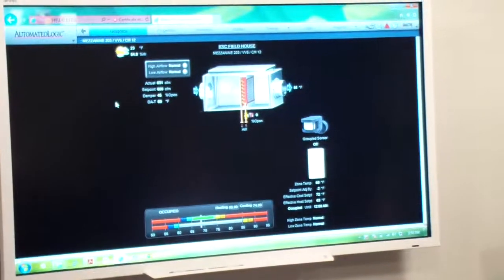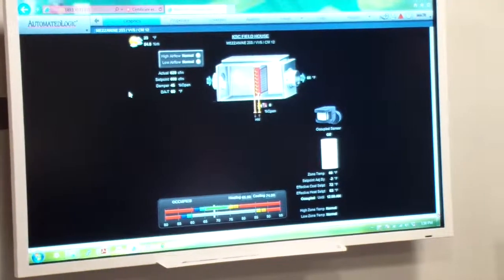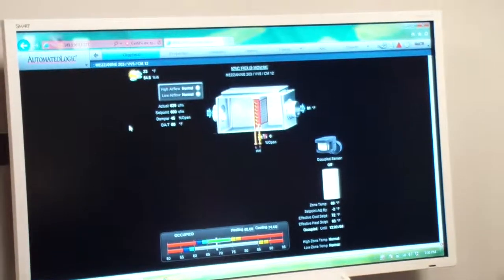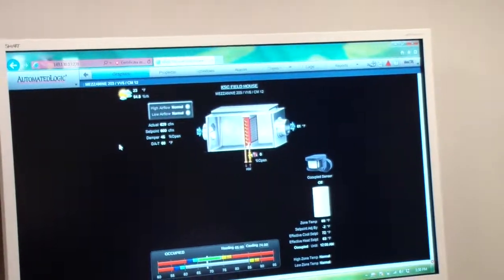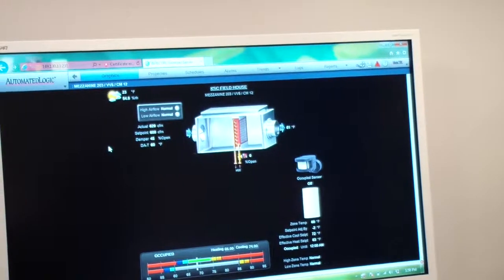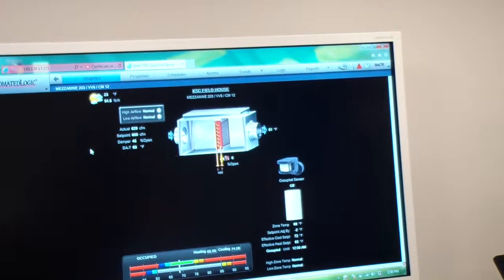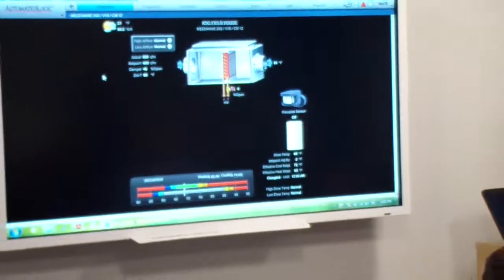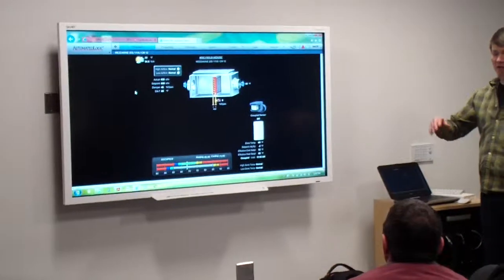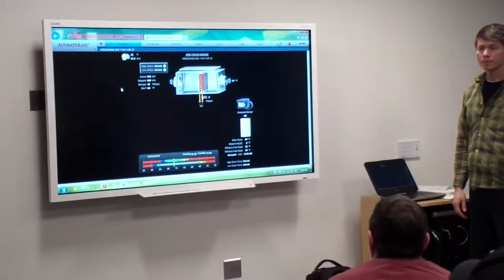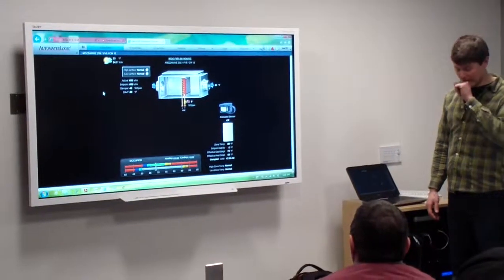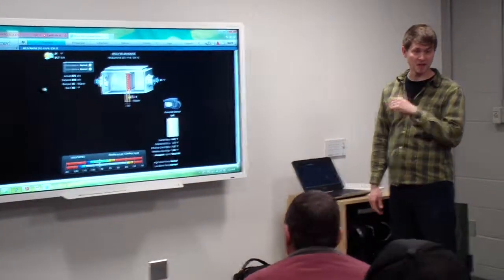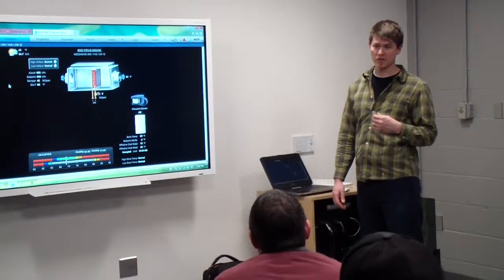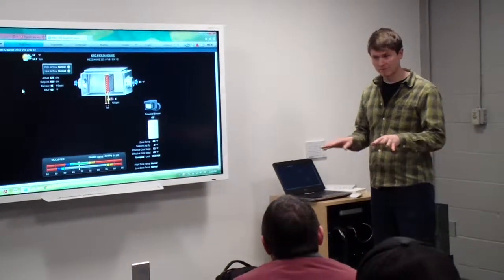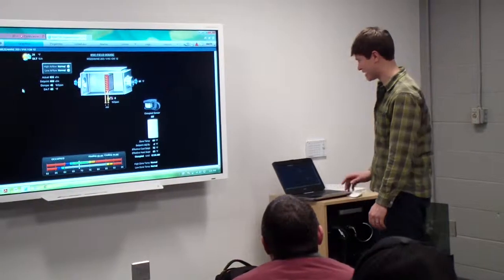When you say thermostat, they're just sensors, there's no remote control. Martha, we just changed those, just let us know. Yeah, but if there's somebody who can't come in and turn them up, is there a slide on those upstairs? It looks like there is, based off of this, that actually is an adjustable set point, but what they have is 2 degrees up or down. Okay, so it's not anything real drastic. 65 would be 63 or 67. It's got a dead band, whatever, 2 degrees, which is adjustable, and if you find that people play with that a lot and you don't want them to, you can actually remove that through software. So they can move it around, but they don't actually get any changes from it.